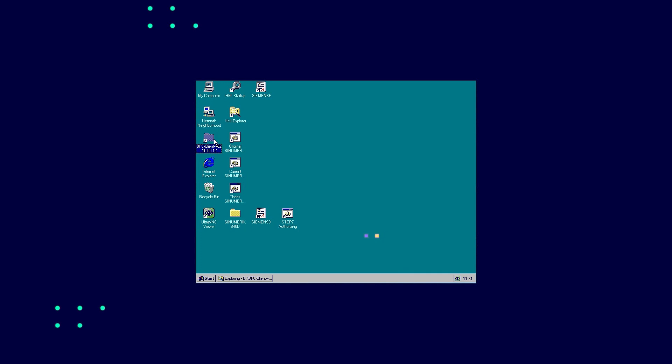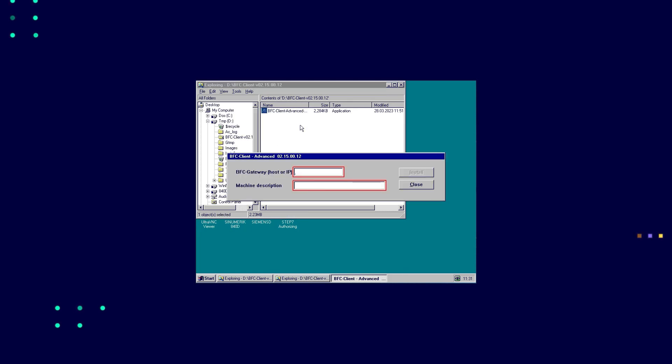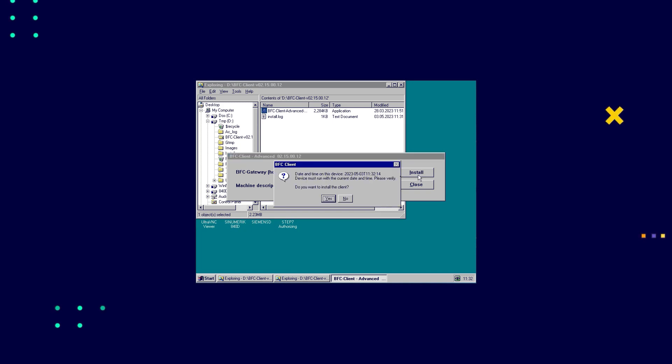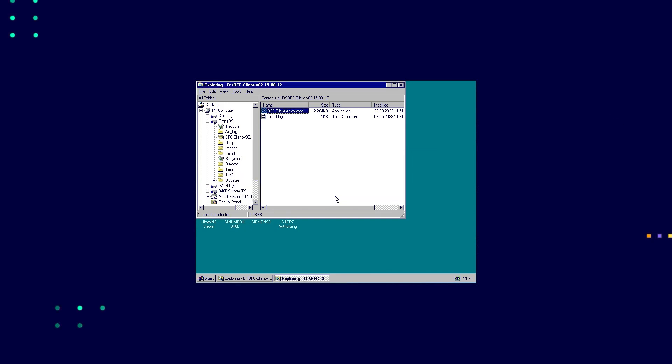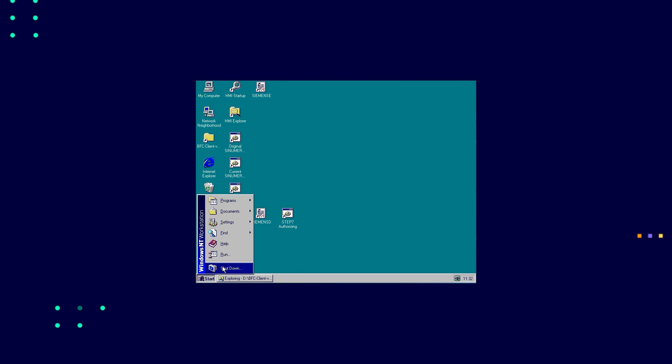To do this, transfer the setup file to the machine in advance via USB stick or configured drive. You can see the operation of the HMI directly via the operation panel as if you were standing right in front of the machine. We assume here that you are already in service mode. Run the appropriate setup file, enter IP host and machine description. Restart the HMI in consultation with the operator.